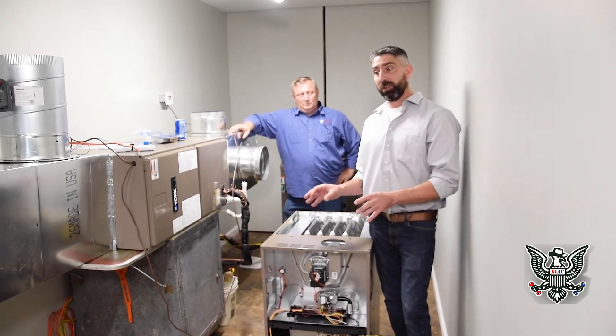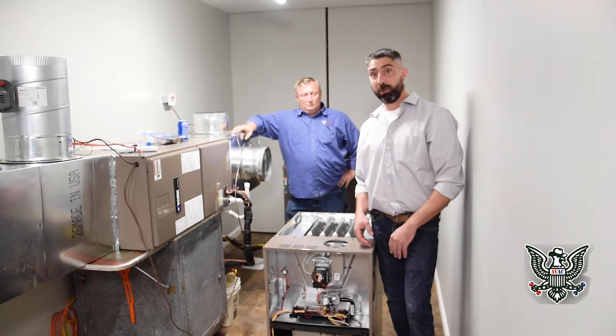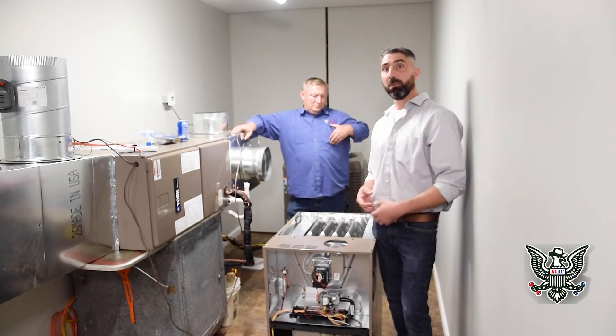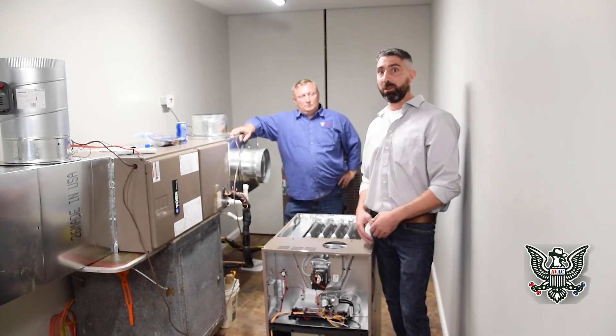A simple look isn't a foolproof operational check, but it's just a quick look — if you look at the furnace and it's got a good, nice, steady blue flame, that's a good indication that your furnace is operating well as far as combustion goes.